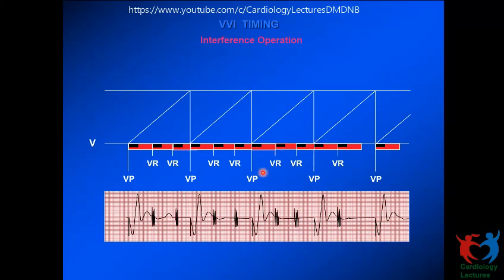Yes. So all the refractory period corresponds to ignoring; sensing and ignoring correspond to the intrinsic event. If the pacemaker has to pace inside the refractory period, if we have set it that way, it will pace during that. So for example, let's take this refractory ventricular sense. It started another refractory. Let's assume this refractory has not ended before the lower rate timed out. So at the end of the lower rate timeout, it will actually pace.